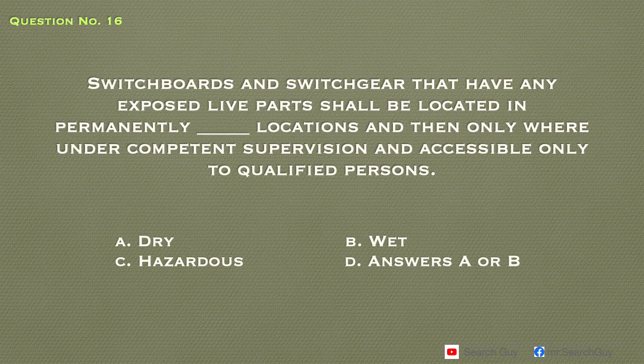Question number 16. Switchboards and switchgear that have any exposed live parts shall be located in permanently blank locations, and then only where under competent supervision, and accessible only to qualified persons. A. Dry. B. Wet. C. Hazardous. D. Answers A or B. Answer. A. Dry.